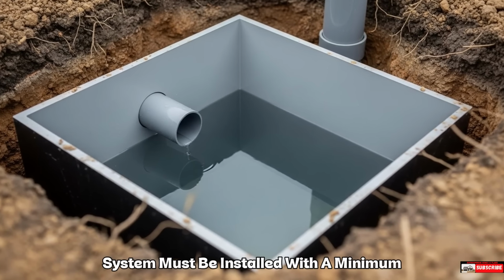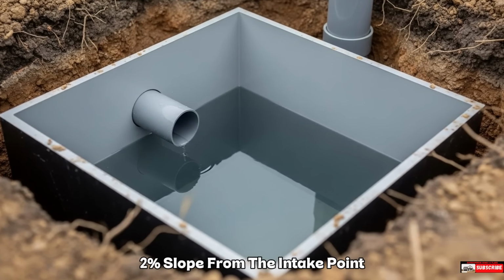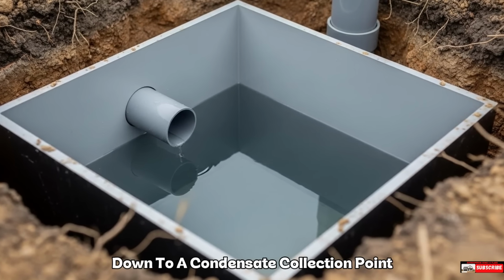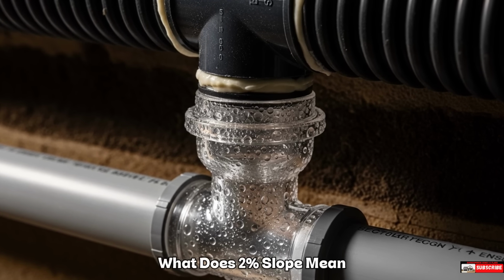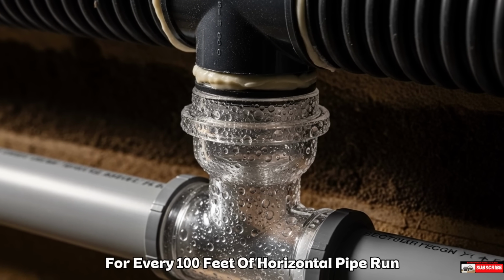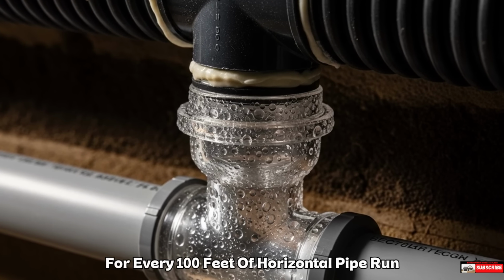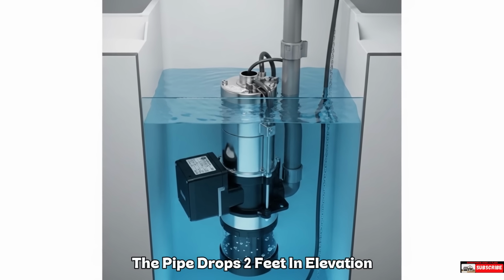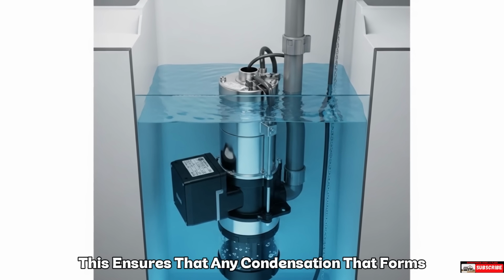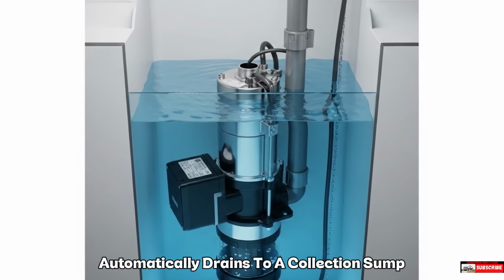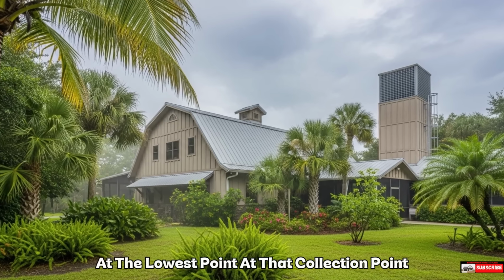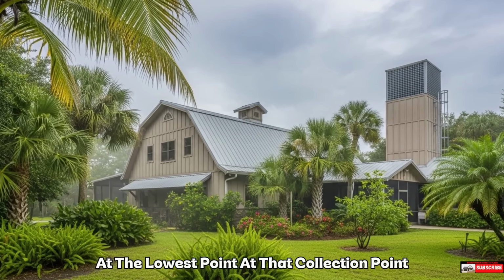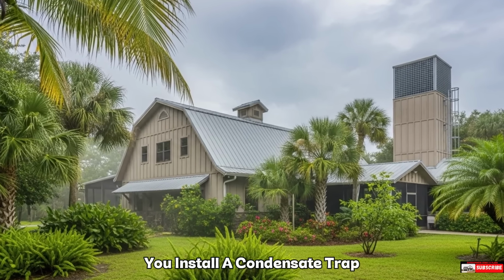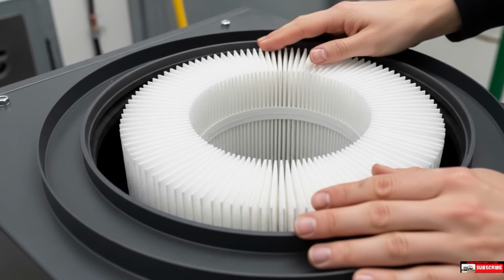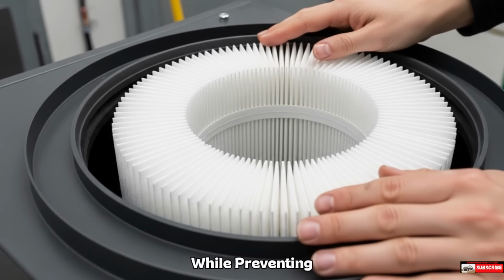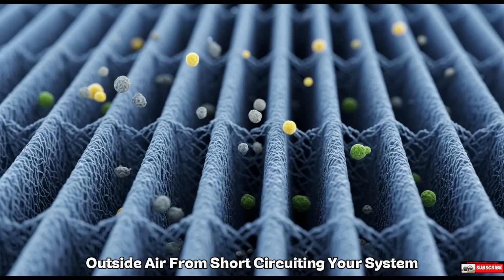Every earth tube system must be installed with a minimum 2% slope from the intake point down to a condensate collection point. What does 2% slope mean? For every 100 feet of horizontal pipe run, the pipe drops 2 feet in elevation. This ensures that any condensation that forms inside the pipe automatically drains to a collection sump at the lowest point. At that collection point, you install a condensate trap, similar to a plumbing P-trap. This trap allows water to drain out while preventing outside air from short-circuiting your system.